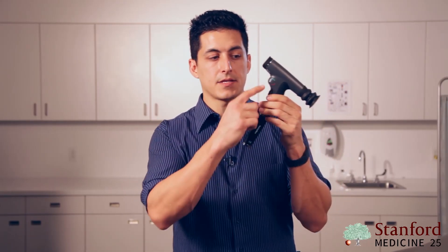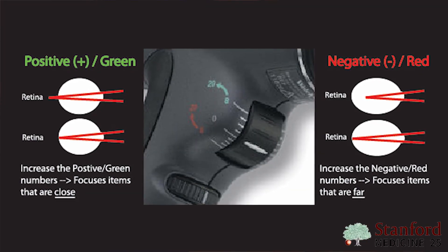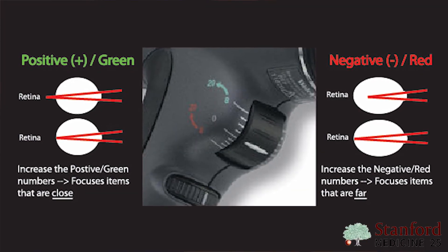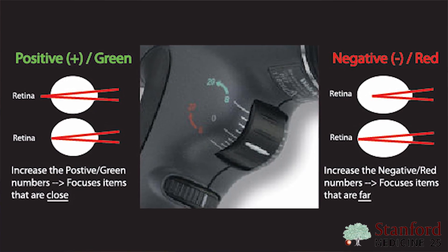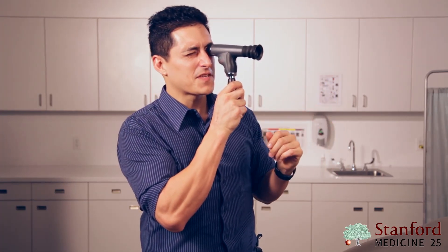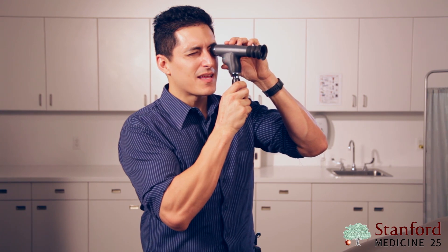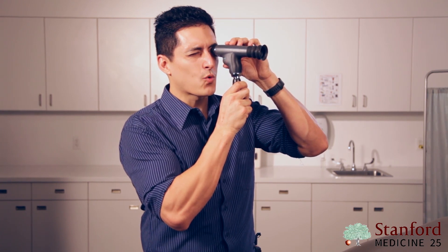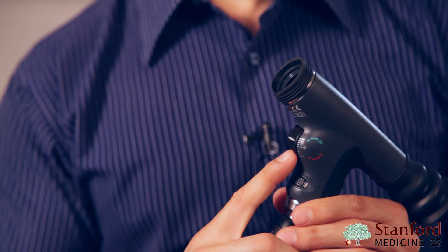The third and final setting to know about the panoptic is these numbers, which allow you to focus if you or your patient are too nearsighted or too farsighted. This setting can actually be used to figure out your prescription — just look through the scope at something about 10 to 15 feet away and move the knob until it comes into focus. If it focuses toward the red setting, that's your prescription in diopters for someone who is nearsighted.